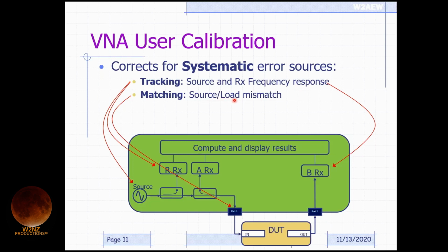Also, what's called source and load mismatch. Ideally you'd have a 50 ohm output impedance and 50 ohm input impedance at these ports, but if they're not exactly that, you're going to have some reflections at those ports, even not including the DUT. The user cal can account for that, so it doesn't become part of the measurement of your DUT. And then also directivity and leakage.